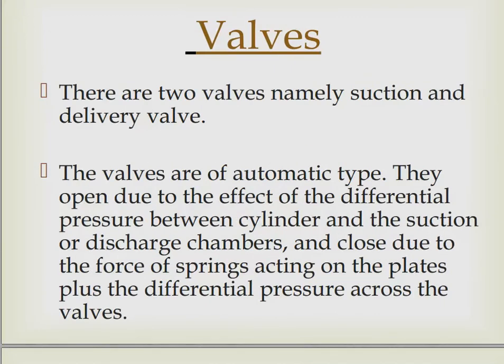Then we have valves. There are two valves, namely the suction and delivery valves. The valves are of automatic type. They open due to the effect of the differential pressure between the cylinder and the suction or discharge chambers, and close due to the force of a spring acting on the plates plus the differential pressure across the valves.